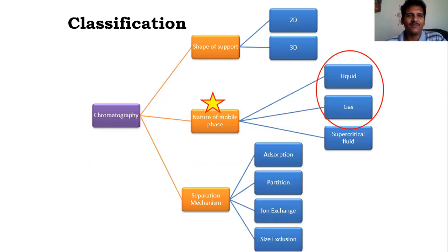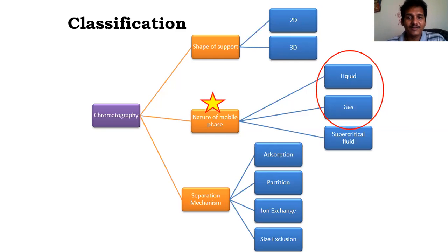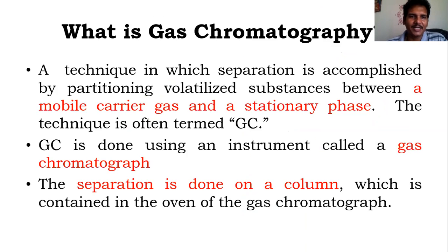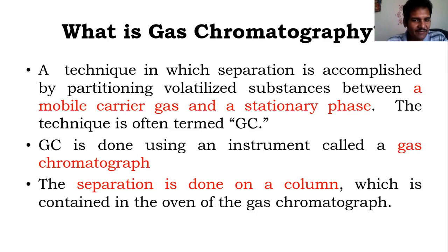Chromatography can be broadly classified based on the nature of the mobile phase — liquid, gas, or supercritical fluid — the nature of the support (2D or 3D), or the type of separation mechanism such as adsorption, partition, or ion exchange. In gas chromatography, the mobile phase is a gas, the separation is done in a column kept in an oven, and the oven plays an important temperature-related role we will explore shortly.